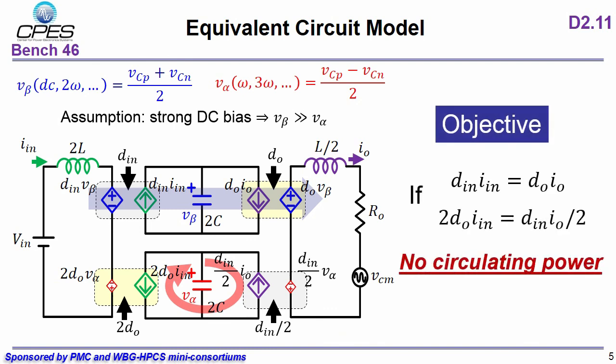When we do a coordinate transformation, the objective to reduce capacitors is very clear. If the two current sources are balanced, which means D-in times I-in equals D-O times I-O, and 2 times D-O times I-in equals D-in times I-O, when these two conditions are implemented, there is no circulating power exists in MMC, which means we can greatly reduce the capacitor.